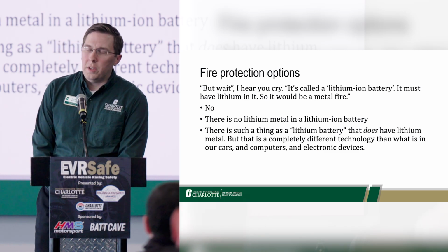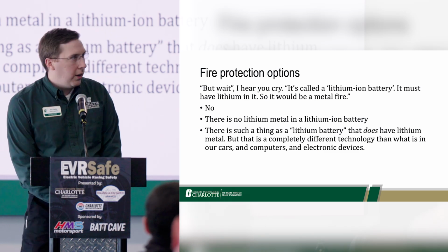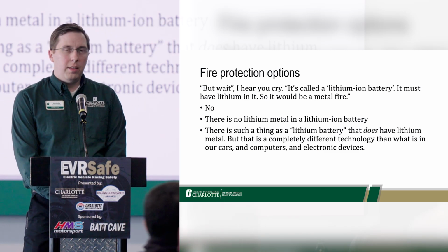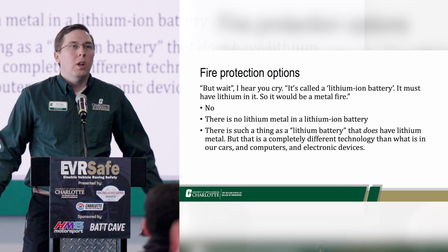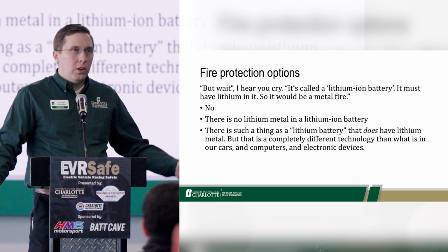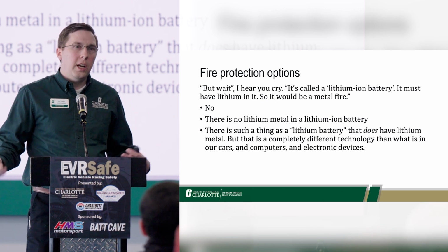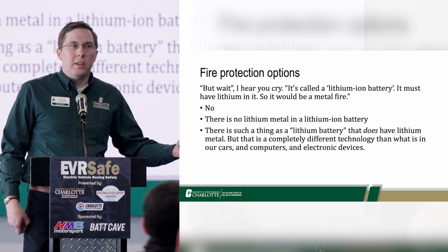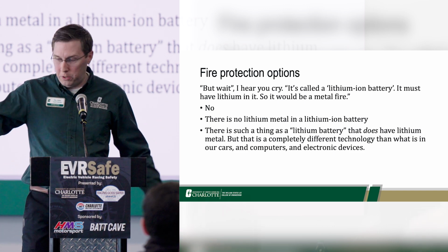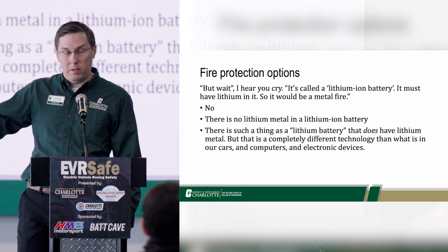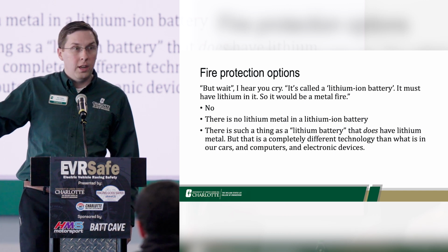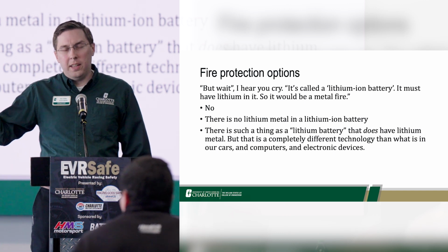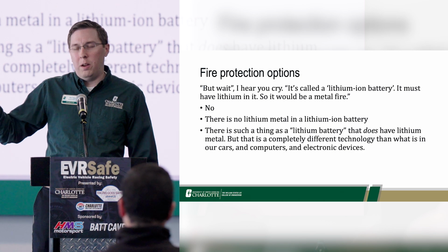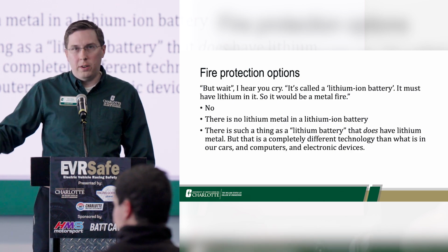But wait, I hear you cry, it's called a lithium-ion battery fire, so there must be lithium in it, right? So people that know enough to be dangerous say, okay, I need a Class D fire extinguisher, one for flammable metals, the big 50-pound yellow monoliths. And again, elemental lithium is not what's happening inside a lithium-ion battery.